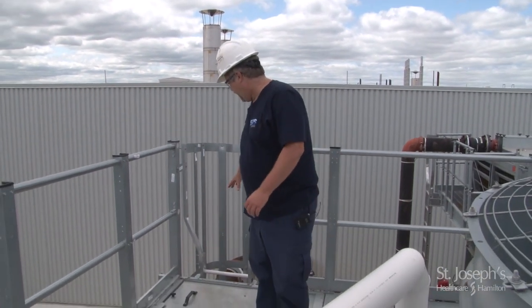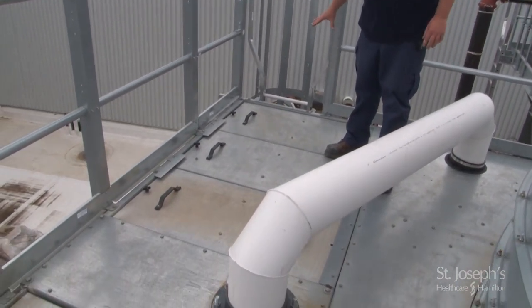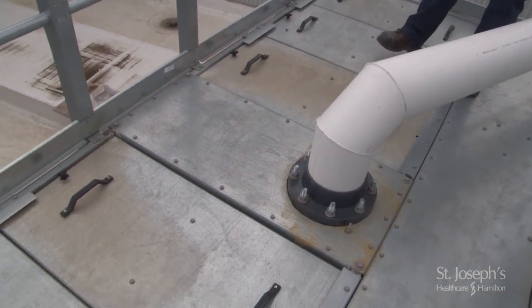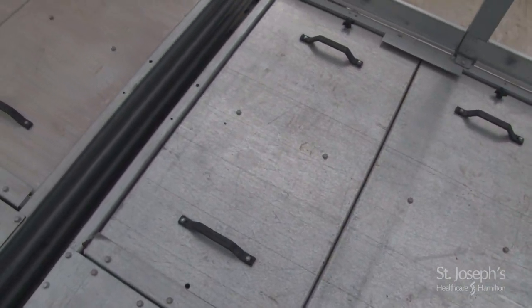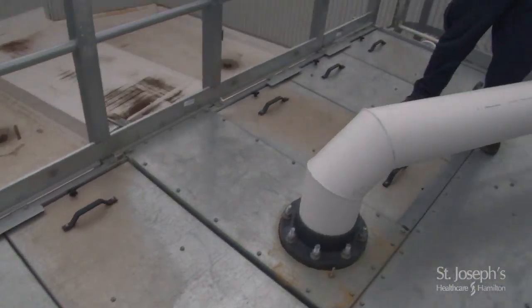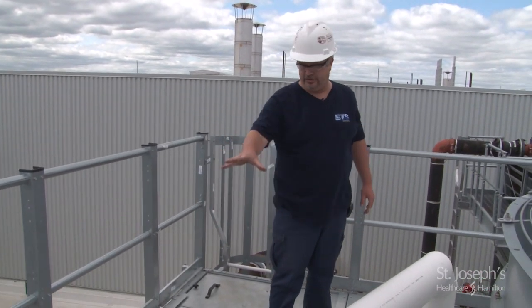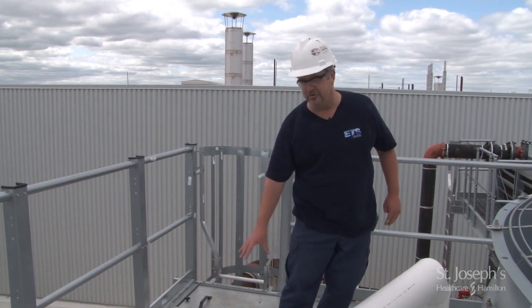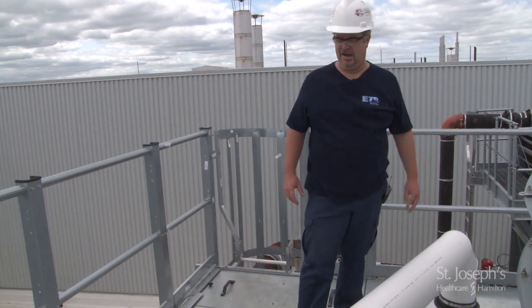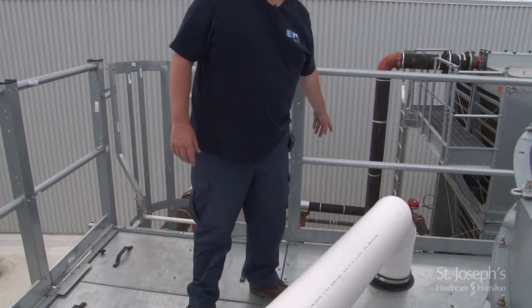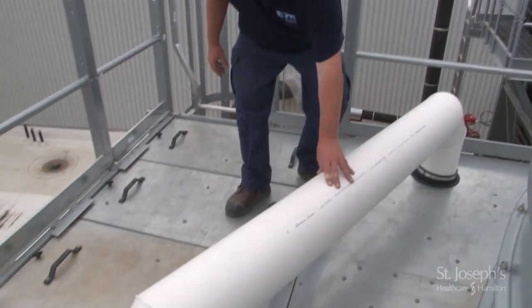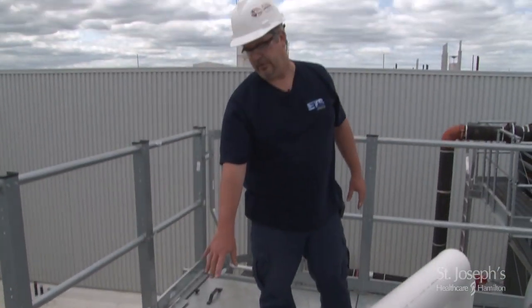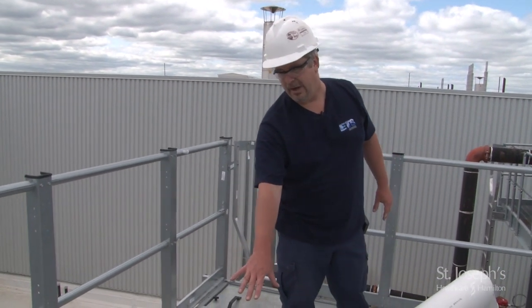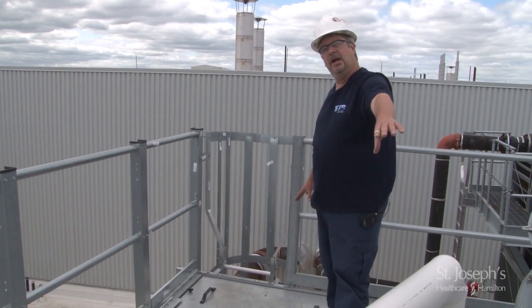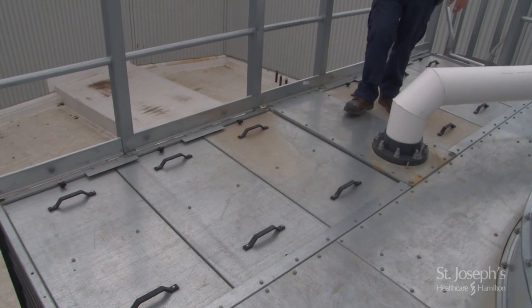We're now on top of the Series 3000 cooling tower. As you can see, what I'm standing on right now is a series of access doors. These doors are what allow you to get in and have a look at the hot water box inside the cooling tower. There's a series down this side of the tower and an identical set down the opposite side of the tower. The water that has been pumped up through the pipes we looked at earlier flows in through these pipes, enters the top of the basin, or the hot water basin, from the middle, and then disperses itself evenly across this bank of hot water box.